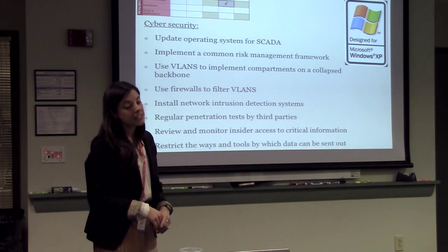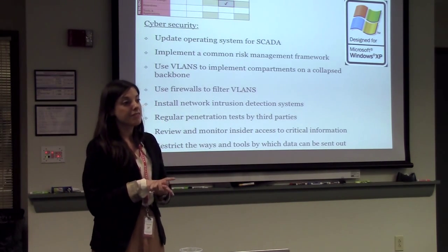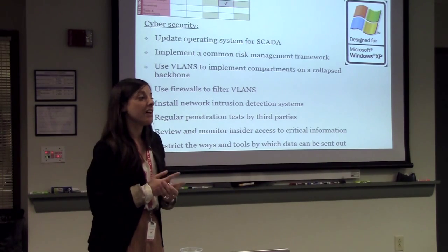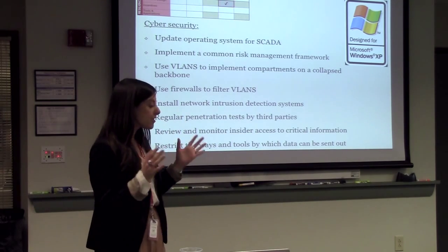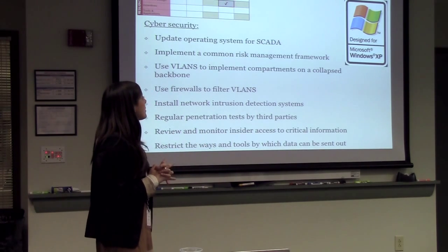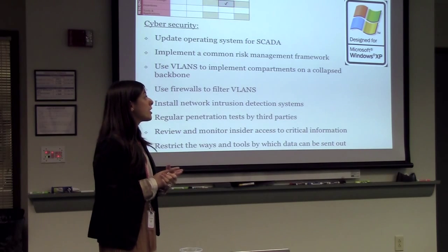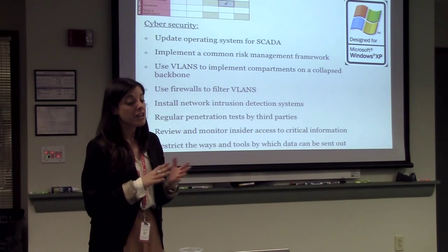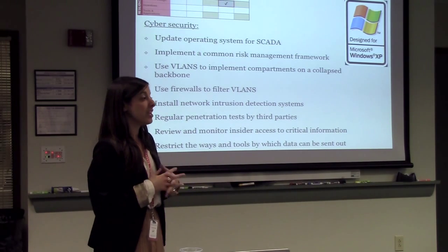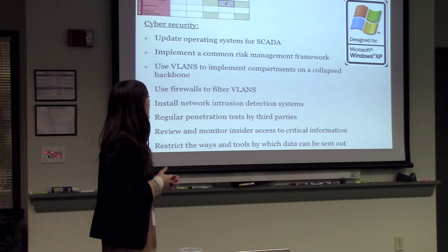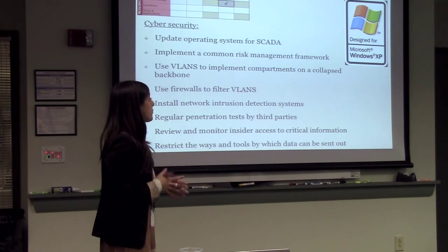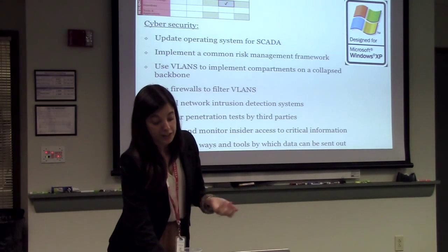And then cybersecurity. We found that nowadays it's a critical issue to be addressed, moreover in this information era. We found that these SCADA systems are working with Microsoft XP, which is very vulnerable to being hacked. So our suggestion is to update the operating systems on the SCADA system. We also made a list of recommendations that could be implemented by Logan or by third parties that are specialized in these kinds of issues.